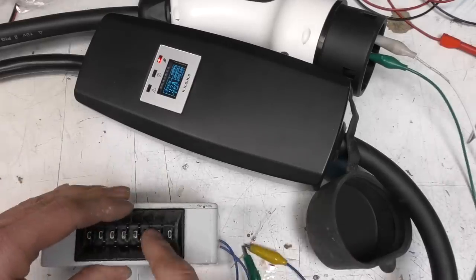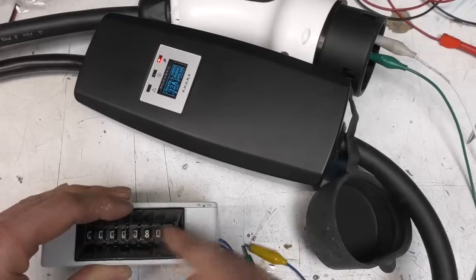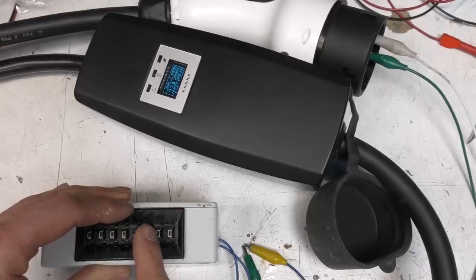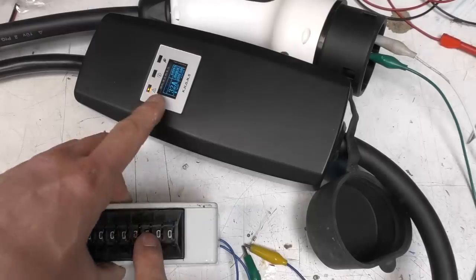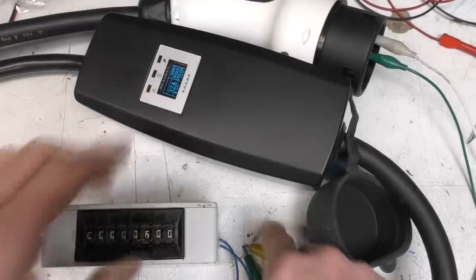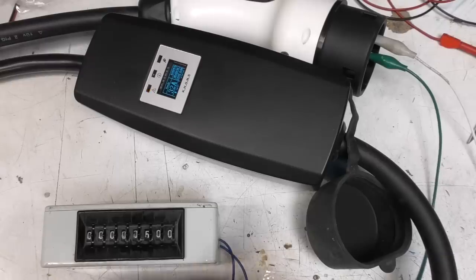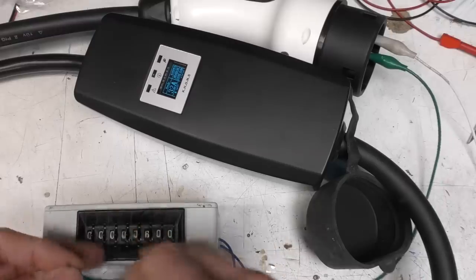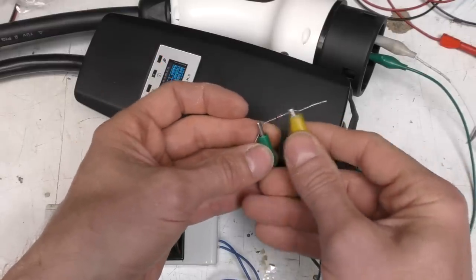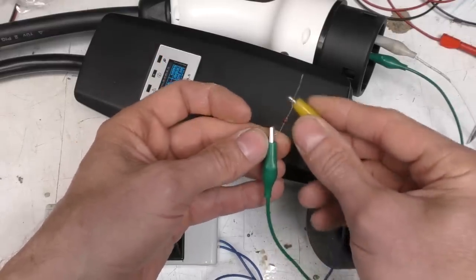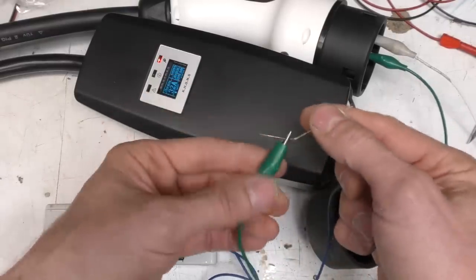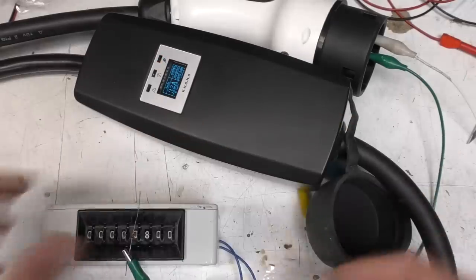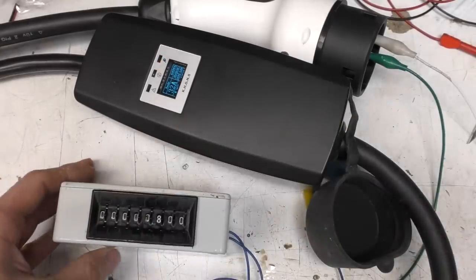Let's see what happens if we reduce the resistance to emulate, for example, a shorted cable. Okay, so if we reduce the resistance too low, then it does actually give us a fault indication. So a shorted cable will make it not turn on, but the fact that it's not caring whether that diode's in circuit or not means that it isn't compliant with the charging spec that it's claiming to be compliant with, and that's one safety feature that it doesn't implement correctly.